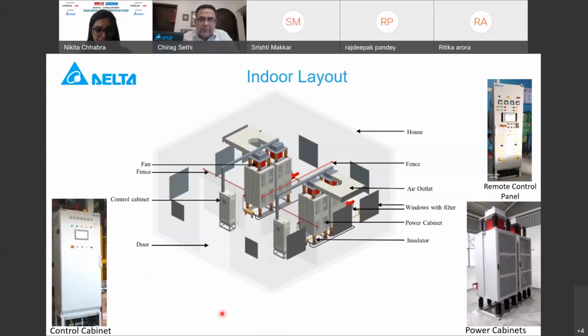Here you see a 6 MVA configuration where you have 2 pairs of panels, each of 3 MVA rating. We also have a remote control or annunciation panel inside the railway control room, where all fault logs and system status are reported. From here, it is also connected to the RTU, so we are able to integrate into the SCADA, and at the headquarter level in the TPC, they are able to see the performance of the system.